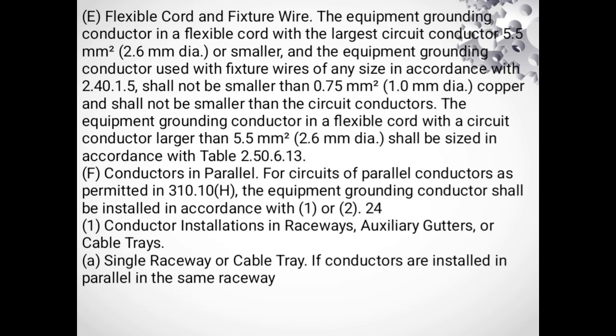E. Flexible cord and fixture wire. The equipment grounding conductor in a flexible cord with a circuit conductor of 5.5 mm² (2.6 mm dia) or smaller, and the equipment grounding conductor used with fixture wires of any size in accordance with 2.40.1.5, shall not be smaller than 0.75 mm² copper and shall not be smaller than the circuit conductors. The equipment grounding conductor in a flexible cord with a circuit conductor larger than 5.5 mm² shall be sized in accordance with Table 2.50.6.13.